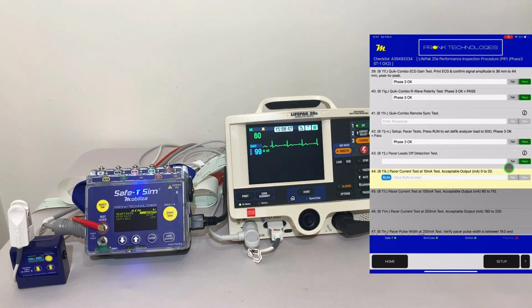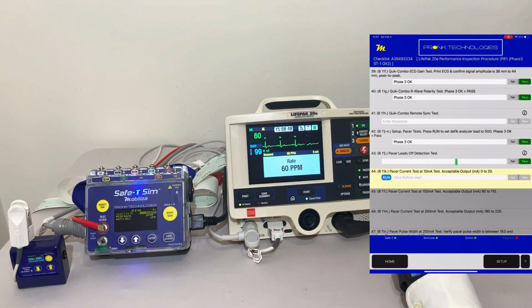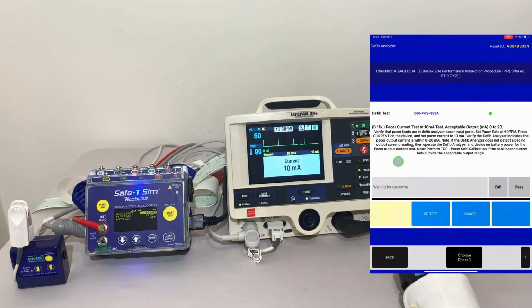So we're going to put it in pacer mode, and we're going to set it according to what is required here. In this case, we want to set it to 10 milliamps. So we're going to go ahead and adjust that current on the defib, and we execute the test. In this case, we're waiting to do a measurement. So the Mobilize app has instructed the defib analyzer to take the measurement, samples it, and returns the result here.